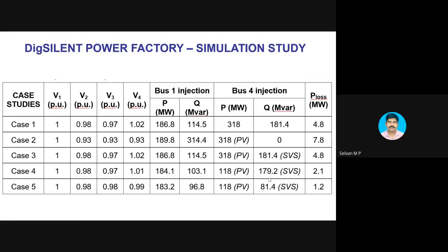So I need a dynamically variable reactive power source, not a fixed one. When the word reactive power comes to mind, immediately the device which comes to our mind is the capacitor. A capacitor is a reactive power source, of course, but it is not dynamically variable. It can provide its rated reactive power only when the voltage is at rated value. If I buy a 1 MVAR capacitor bank, it can supply 1 MVAR when the voltage across it is 1 per unit. If the voltage reduces, the reactive power output from the capacitor also reduces.